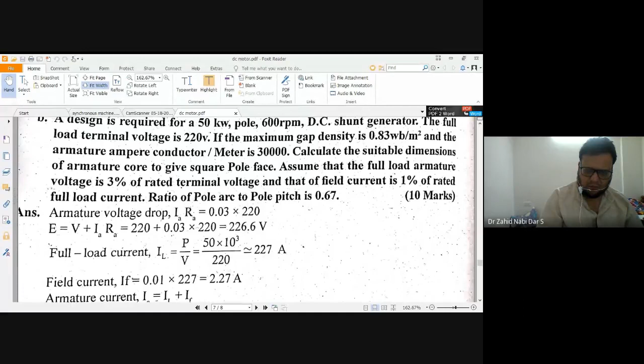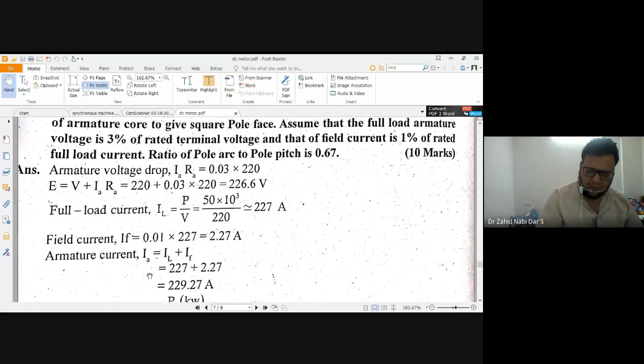Now the field current, it's mentioning the field current is 1% of the rated full load current. So rated full load current you got 227. 1% of 227 is 0.01 into 227, that is 2.27. So you got the field current and you got the load current. Load current plus field current will give you the armature current in case of a DC generator. Now, if it was a DC motor, it would be a different equation. That equation you have to find out.